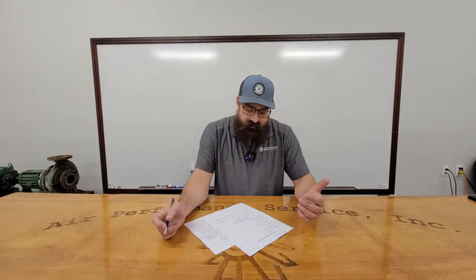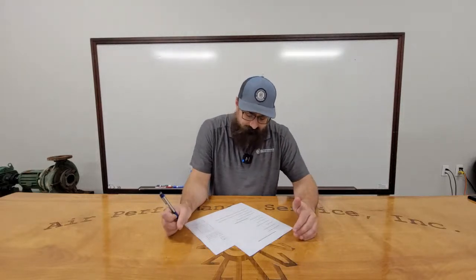If the units are in a building automation system, we would monitor each unit, and if the temperatures start to get high, we would call for the condenser loop to start just to circulate water, and then our tower would stage up based on our set point. So if the water temperature starts to rise, we would start putting water over the heat exchanger and then start ramping fans up based on that set point. Other than that, they're pretty standard, just like a normal split or package unit.